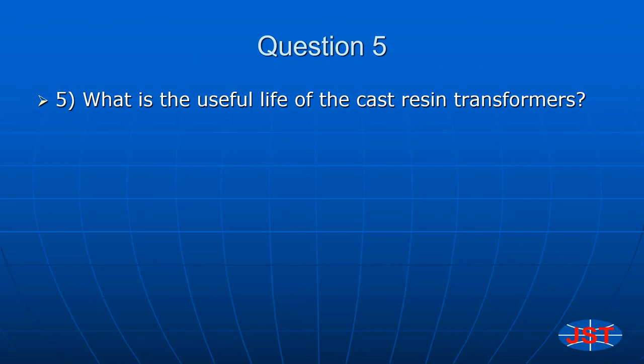The next question is, what is the useful life of the cast resin transformer? That's a tough one to answer. I could see what I see specified a lot. I see 20 and 25 years specified quite a bit, not even sure how that number came to be, but I could tell you, we have things operating out in the field that have been operating longer than that. The key to it goes back to what I think is the operated conditions. Also maintenance has a lot to do with it. While cast requires little maintenance, especially when compared to liquid filled, it still has to be maintained. And now's probably a good time to mention it. Really one of the things, and however often you need to build it into the maintenance cycle, it really depends on the environment you're going to use the cast resin transformer in.